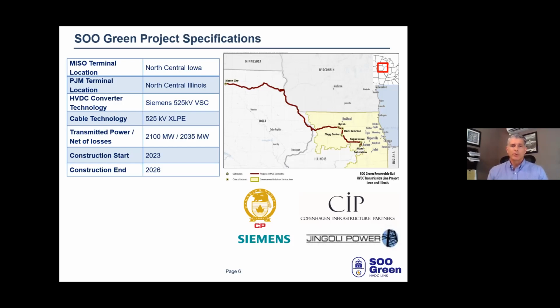We'll utilize two 525 kV cross-linked polyethylene cables—XLPE stands for cross-linked polyethylene. The reason we'll have two cables is because we're DC, one positive, one negative; we don't have three cables like AC. These cross-linked polyethylene cables will be placed within dry PVC conduits. No liquid cooling is required.